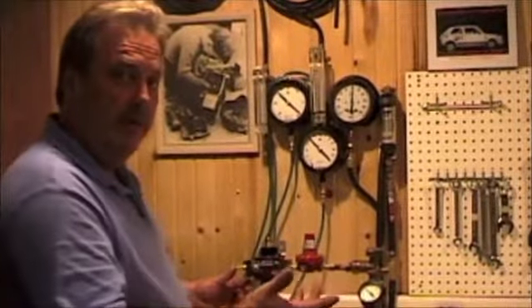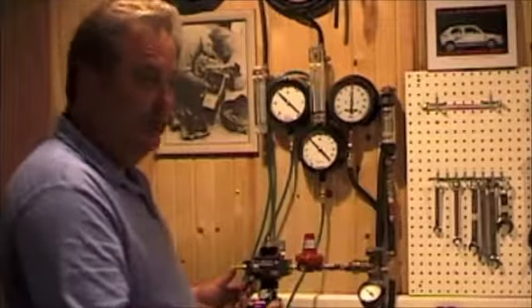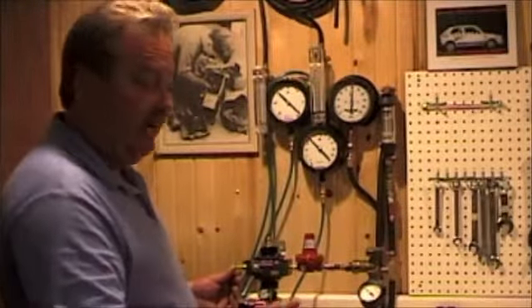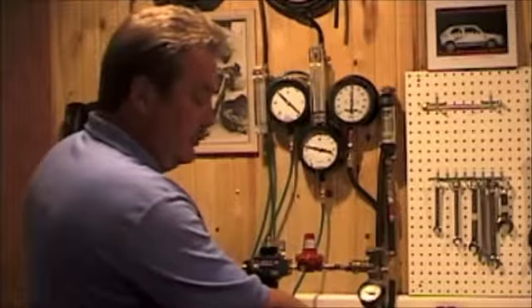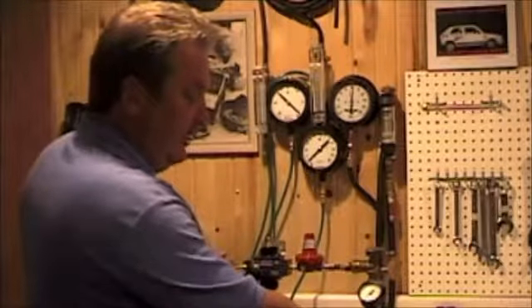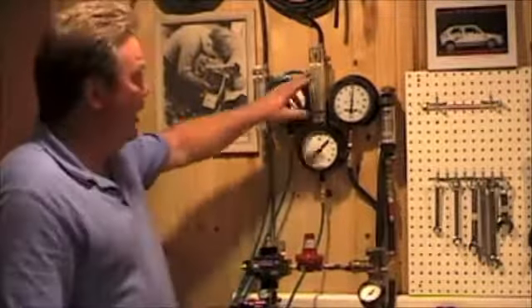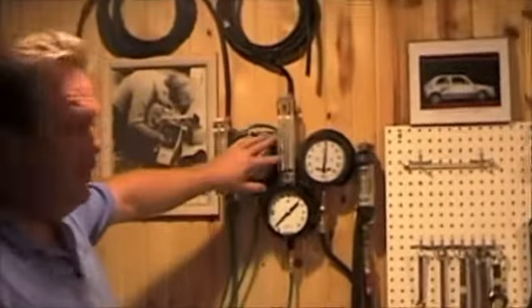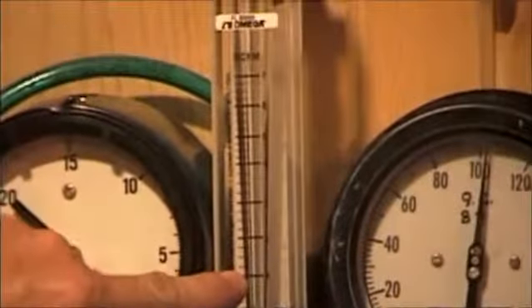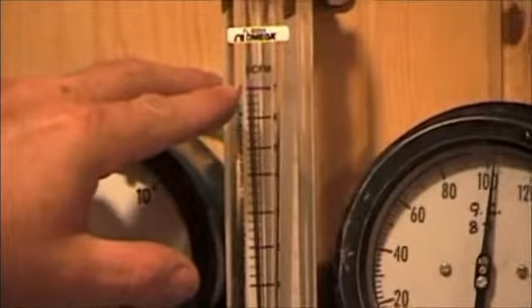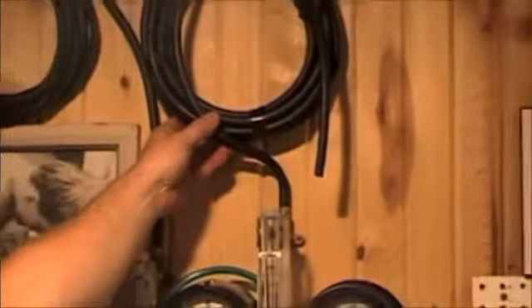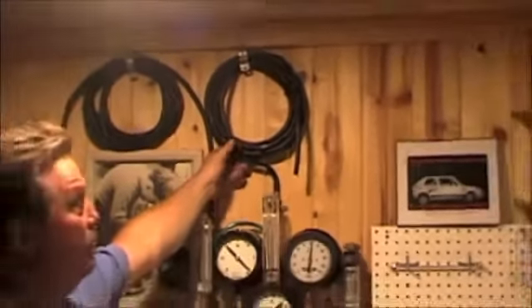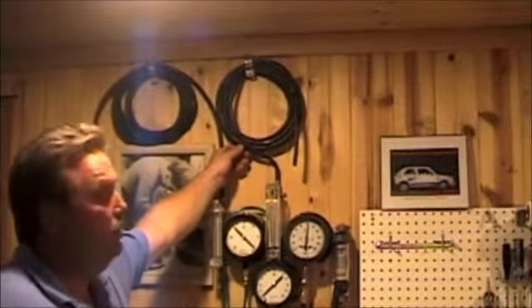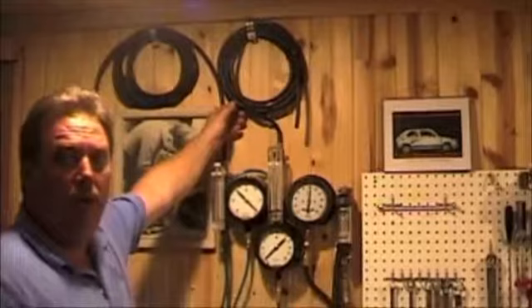Of course, you won't have the luxury of having a flow bench. You'll be doing it with a handheld, but it's still very easy to do. So at this point, I'll drop the pressure back down. I've got a calibrator here on the wall. This one is calibrated 1 CFM to 7 CFM. We've also taken into consideration the length of hose that will be used on the vehicle. We have 25 feet of hose wrapped up here because that will change the amount of propane being delivered.